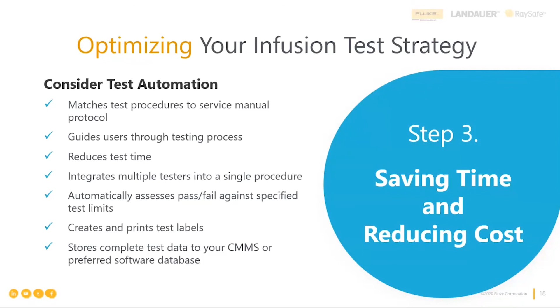Jared, do you have any more comments on this? No, you made a good point, because what are all of the testing instruments that you would prefer to be able to automatically collect measurements from? Well, certainly it's the infusion device analyzer, but it's also your safety analyzer, so your electrical safety. Where your electronic analyzer also measures pressure, you get your flow, volume, and pressure all the time. And each of those parameters could have its own independent testing limit. So in real time, while you're making the measurements, you're also assessing against the testing limits. So it really can speed you up.